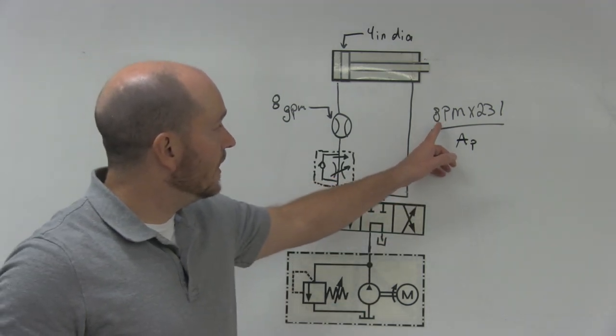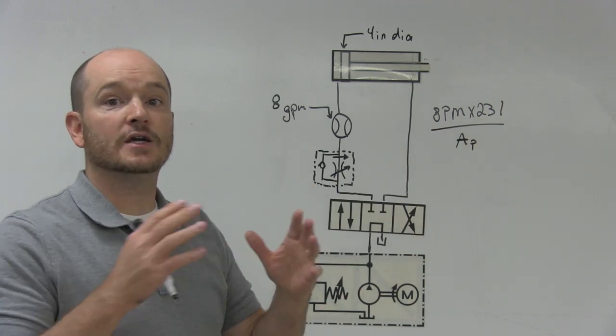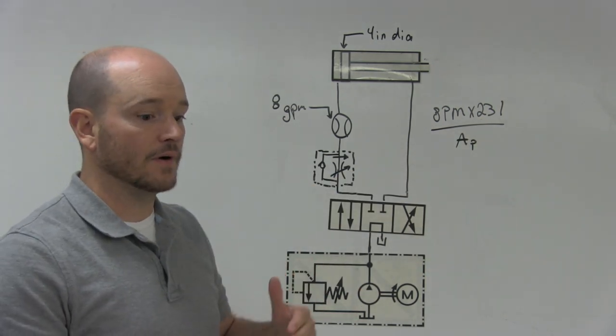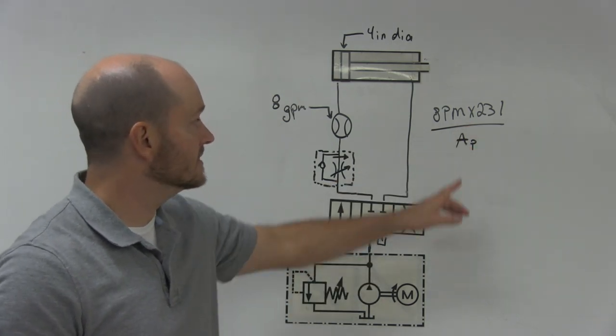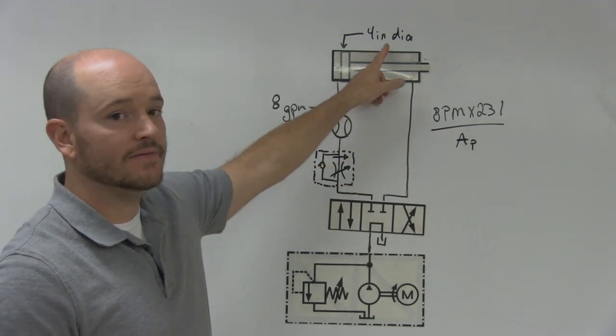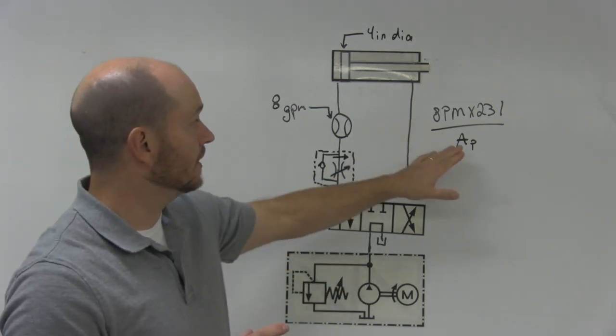Now when you look at this, the point of taking gallons per minute multiplied by 231 is to convert that back to volume. So we're going back from capacity to volume. And that's what this formula does. And then our area of our piston is given here, but it's given in diameter. So the first thing we would have to do, before I start to plug everything in, is to convert this to area.